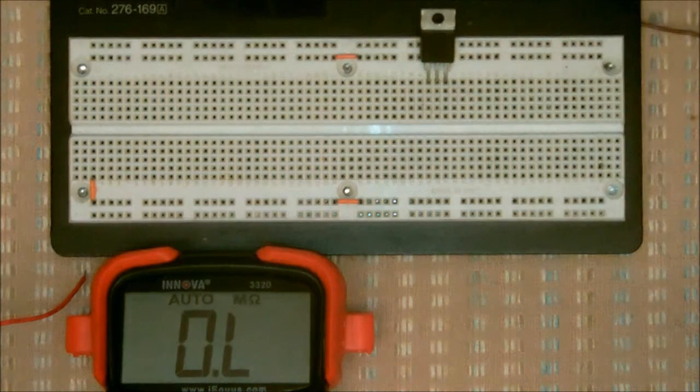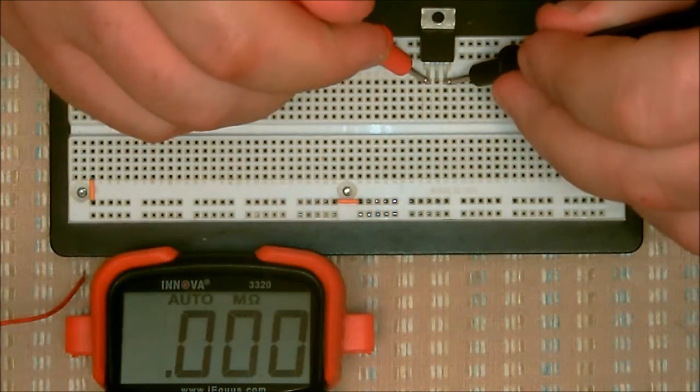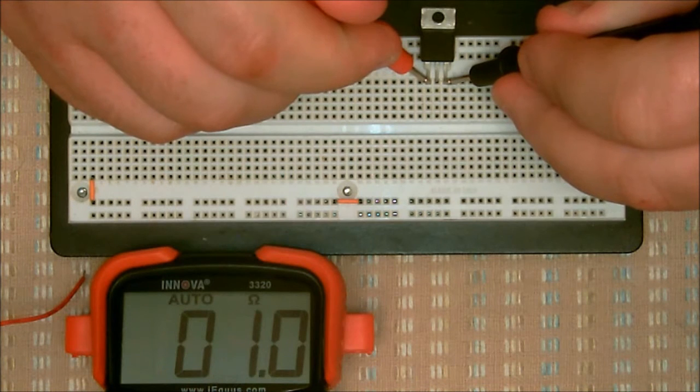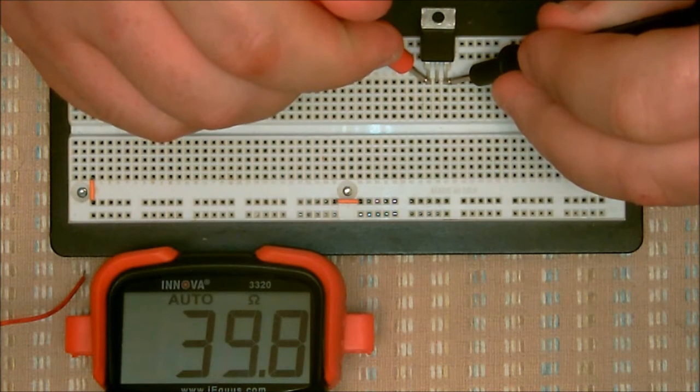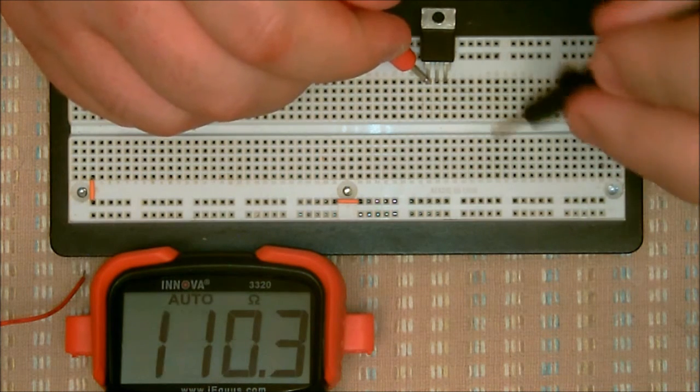You can put the positive lead on the gate and put your negative lead on the MT1. You should read some fairly low resistance like you do here. Not always, but in some cases you will. You can also reverse your leads between the gate and the main terminal 1. Again, you will see that you will get some low resistance. This is okay.